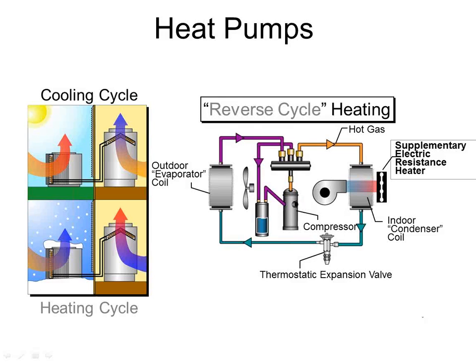All right, so some of the problems with heat pumps in the Midwestern climates over the years: they typically would blow cold air on people, and people didn't like that, right? It was warm enough air to heat your building. Believe it or not, for most buildings, if you have at least an 8-degree difference between your discharge air temperature and your space temperature, you could probably heat most spaces, unless the wall is made of mesh, right? But with a normal constructed wall with single pane windows, if you've got at least an 8-degree delta from supply to space, you can heat it. So in a 75-degree room, if I have 83-degree discharge air, I can heat your room and maintain the temperature of the room. Now, the problem is 83-degree air blowing across my 90-degree skin feels kind of cool, right? So I would like to have warmer air if it's going to blow across me, so I don't feel that quote-unquote cold blow.